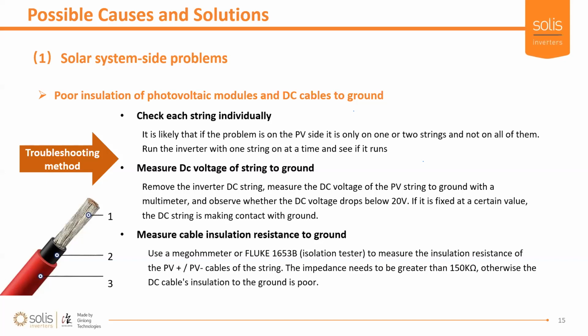Another test to perform is to measure the voltages between PV positive and earth, and then again between PV negative and earth. This is the same test that the inverters do. Doing this test, you can actually find out which pole the fault is occurring on. If you're getting a high voltage between PV positive and earth, obviously the bad insulation problem is on your PV negative pole. And conversely, if the high voltage is on PV negative to earth, your connection is on PV positive.